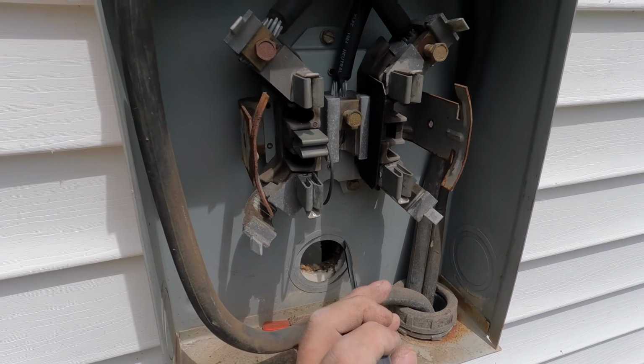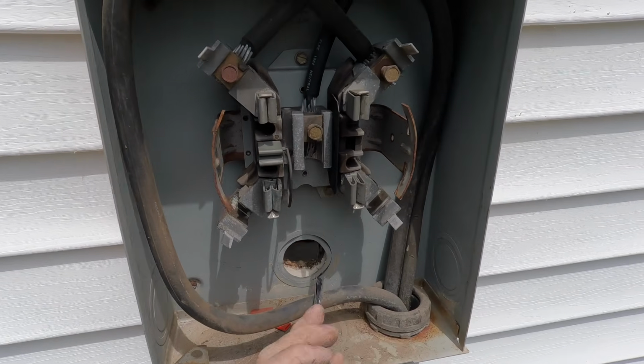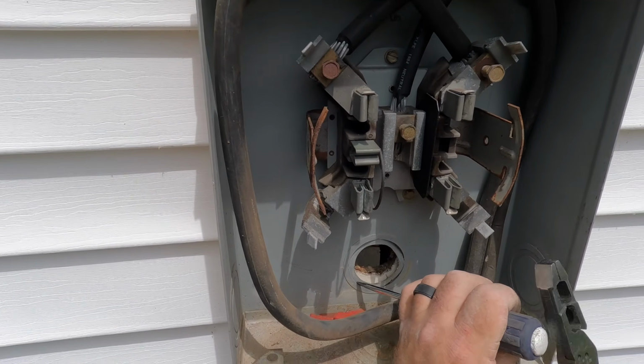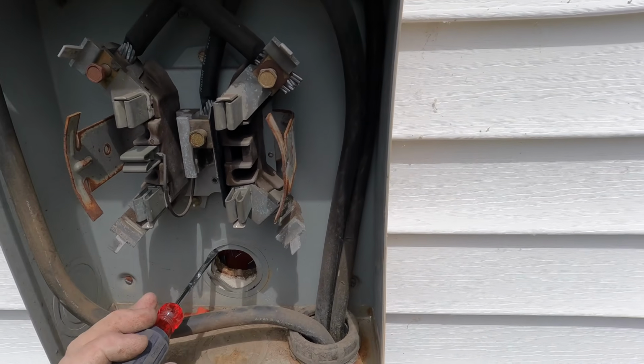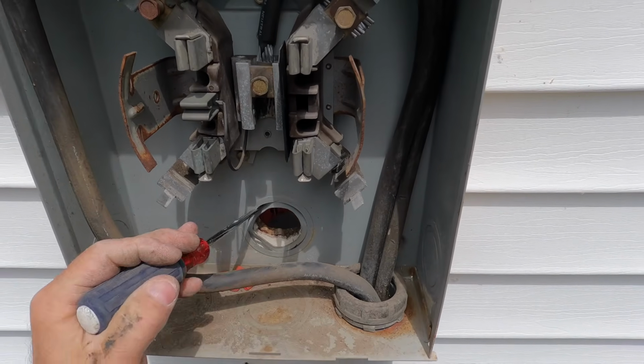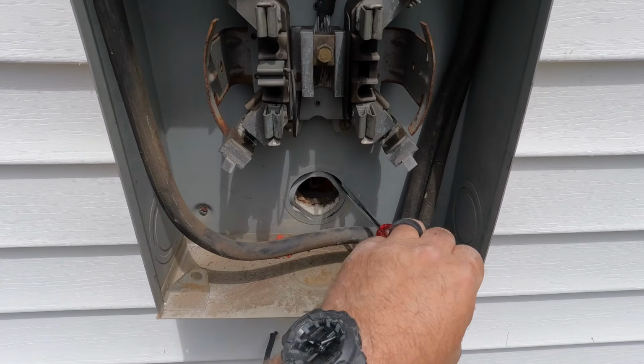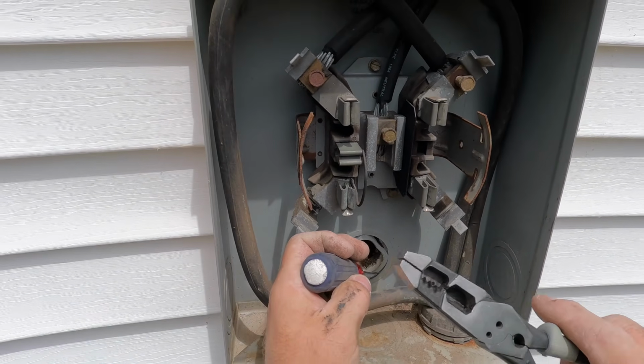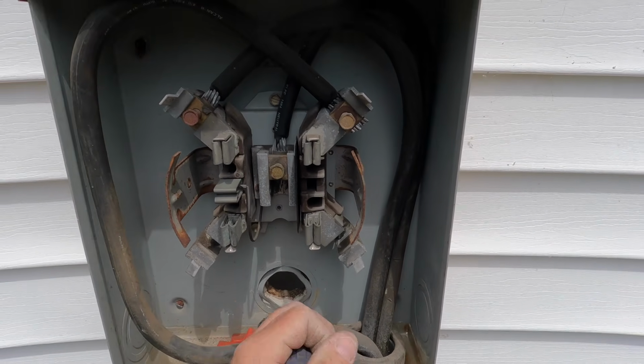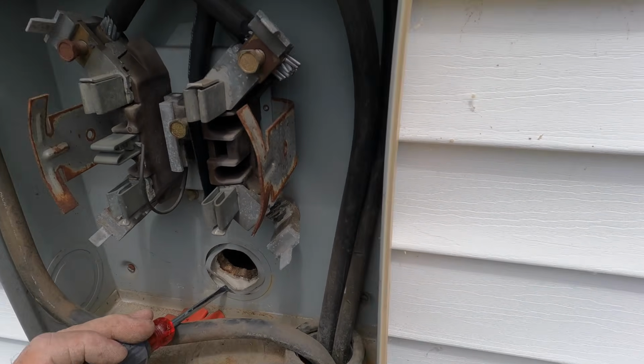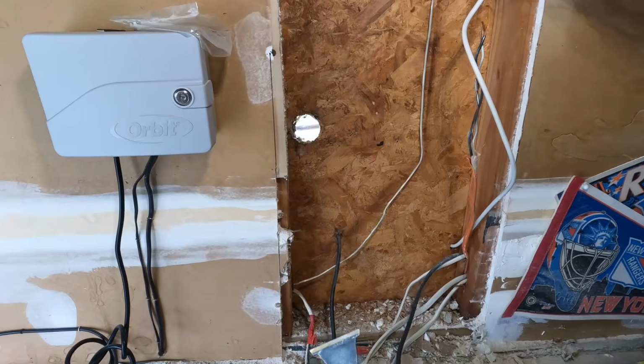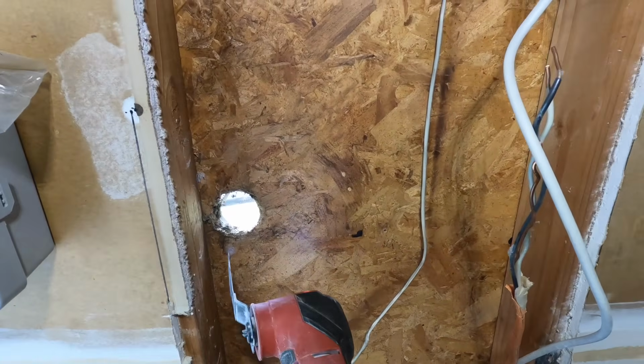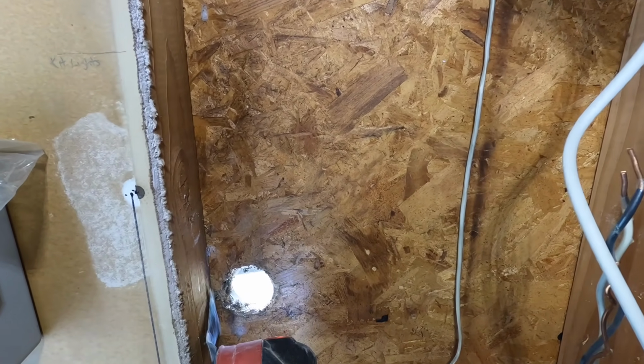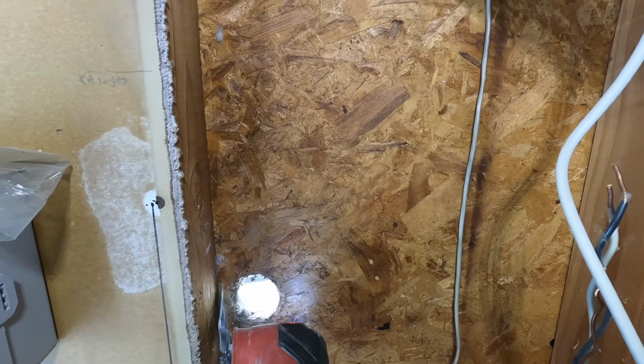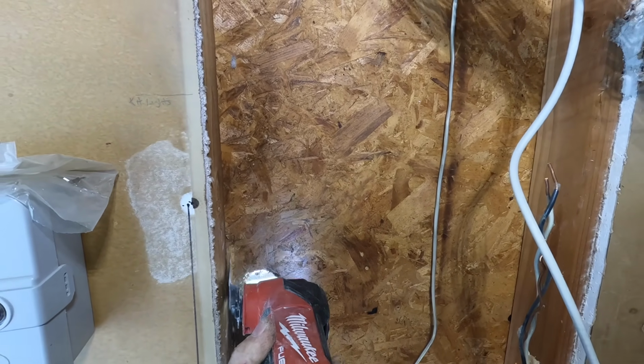Once I get that nipple out, I've got to get rid of this knockout right here and make it large enough so I can fit the 2-inch nipple through there. On the other side, I'll trim out the OSB in a square pattern so I can get the nipple in there with the lock nut. There won't be any problem making a mechanical connection between the meter and the new 200 amp main breaker panel.